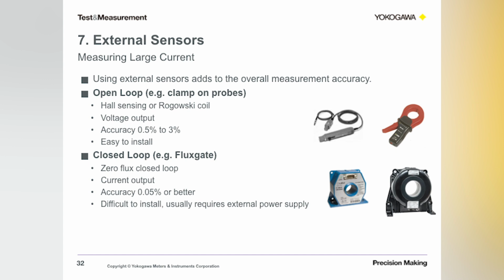The other type is the closed loop type. Example, flux gate with zero flux closed loop measurement circuits. These usually have a low current output on the secondary side that can be directly connected to the current input terminals of your power measuring device. They're highly accurate, with an uncertainty of 0.05% at full scale, depending on which ones you use. But usage-wise, they are a little difficult to install and require a little bit of pre-planning to make your connections, because before you connect, you have to make sure that your wires are passed through the donut hole, as you can see in the example here. They also require an external power supply, so they need some kind of matching power supply, either provided by the measurement instrument or an external box.